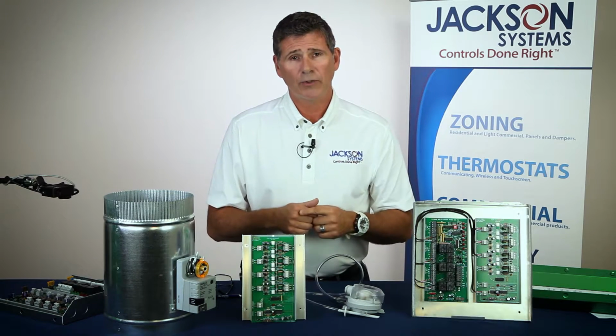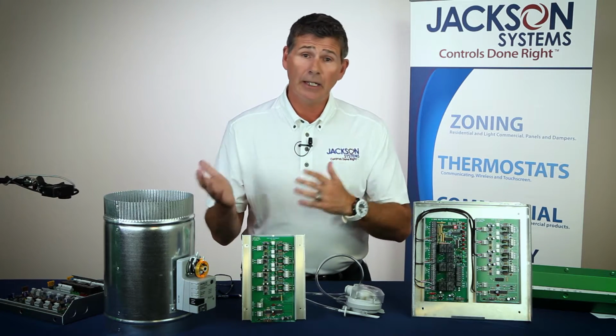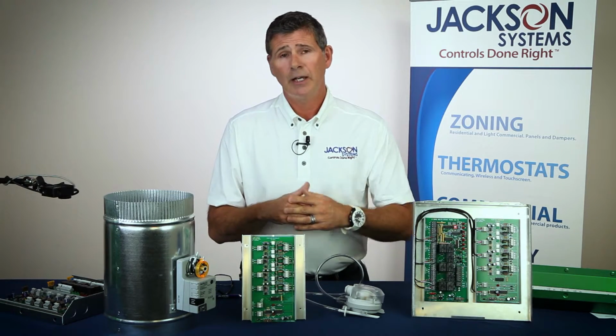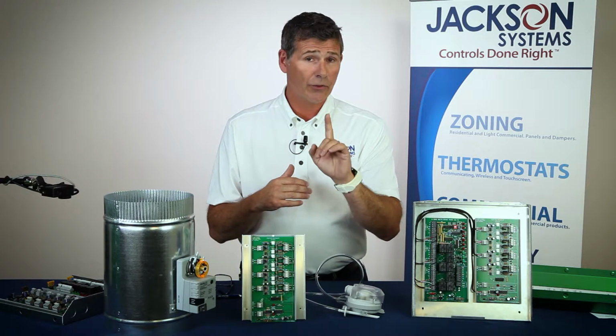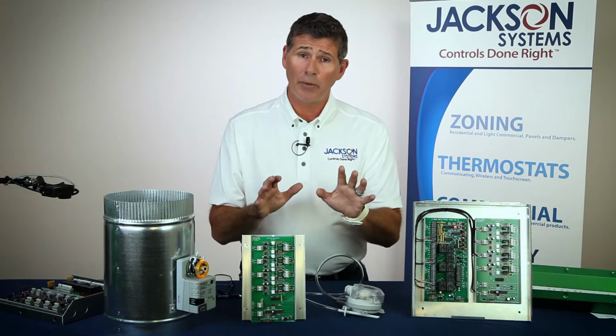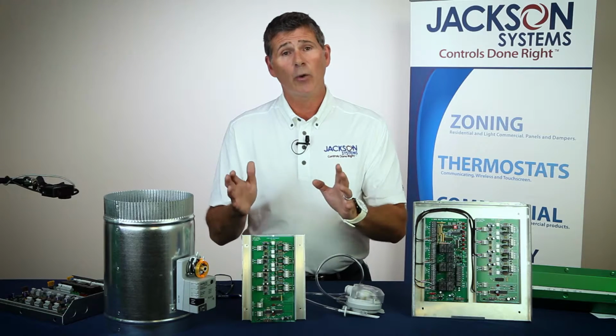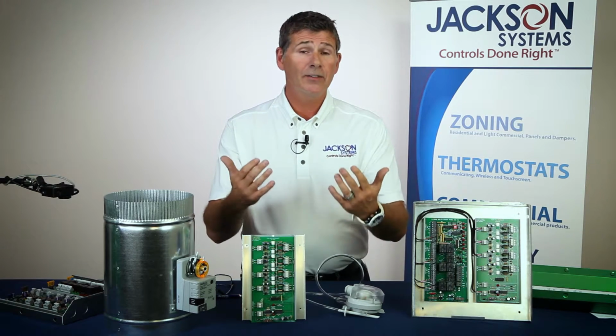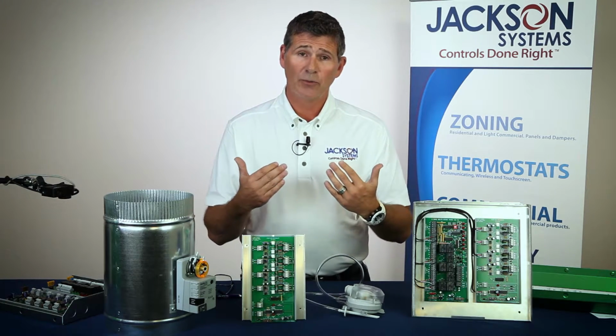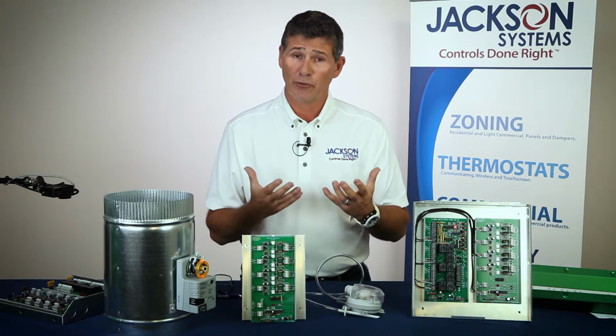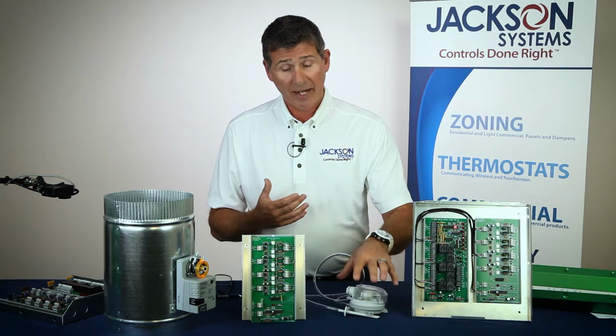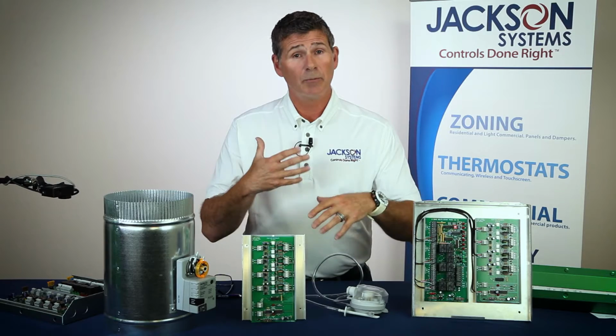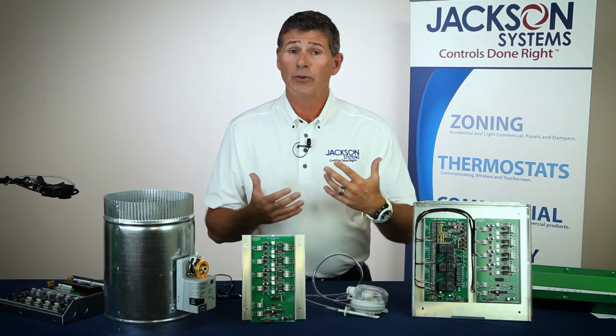Now zone 1 goes ahead and calls. Whether this is a heating or a cooling call makes no difference. So zone 1 is going to call, and zone 1 damper is going to remain open. The other 2 dampers are going to close. Now this is that point in time where those 2 dampers close that you begin to get static pressure throughout the system. And the static pressure control sensor is beginning to monitor that static pressure as it rises.